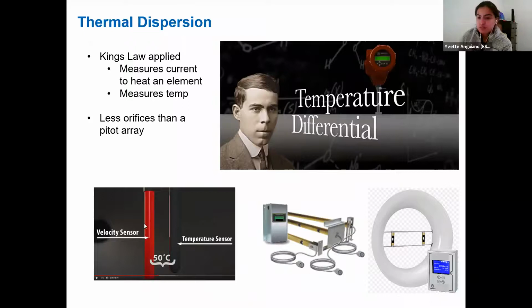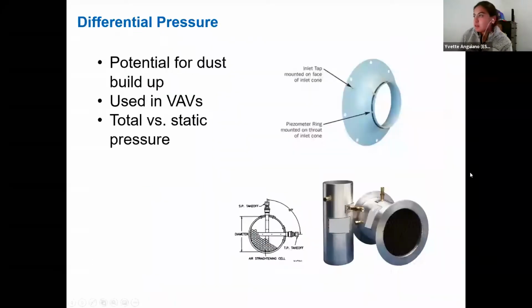Lastly, I want to go into the pros of this device, which is that with a thermal dispersion device, there are fewer orifices compared to, say, the pitot tube, which minimizes clogging from dust. And so going into our next application, we've got differential pressure. We have this piezometer ring, which we'd likely see at the inlet of the fan, as compared to the other ring that we saw for the thermal dispersion application. And then we've also got the pitot tube application here.